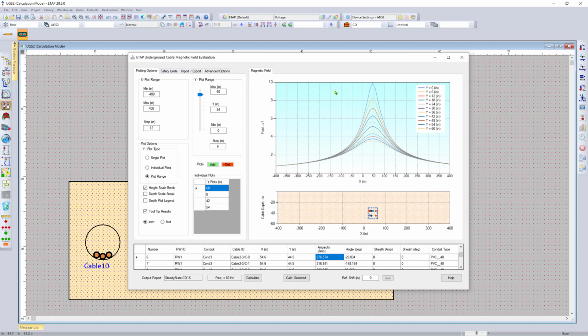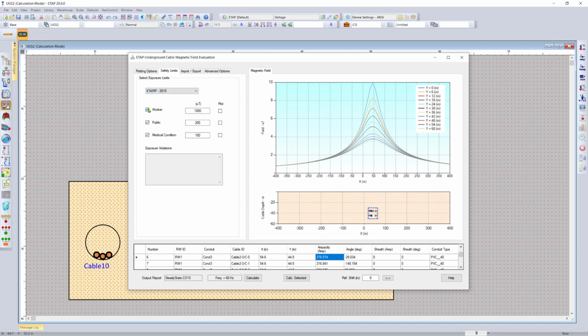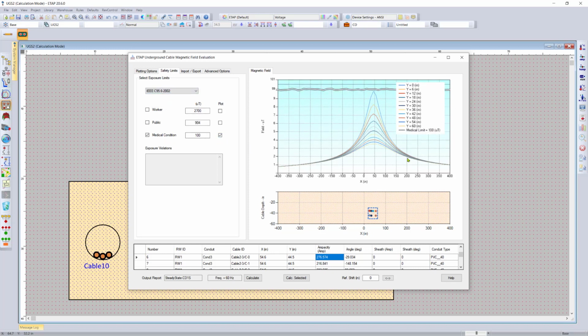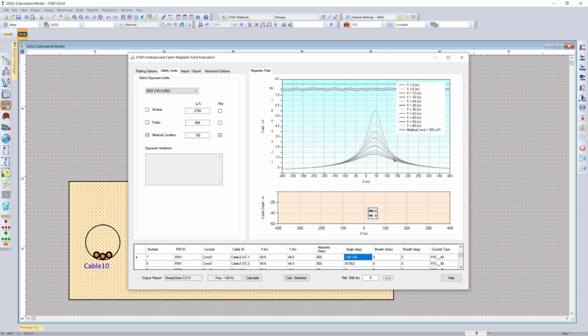You can then compare the magnetic field strength versus the safety limits. By simply selecting the safety limit that you want to comply against and the compliance standards, you can then go ahead and plot these values directly onto the chart. So you can get a very simple and clear safety line and the actual magnetic field strength associated with that particular raceway. As expected, if the intensity of the magnetic field is to be recomputed, we re-enter the ampacity or we recompute based on different scenarios. And we can see, based on the change in the ampacity of the current going through the conductor, the change in the field strength directly onto the diagram.